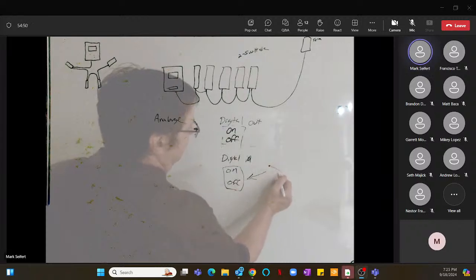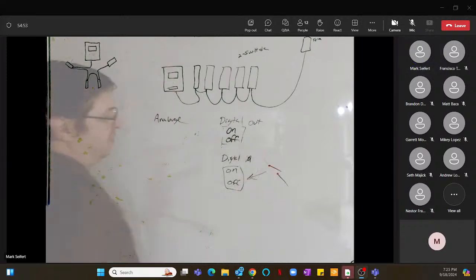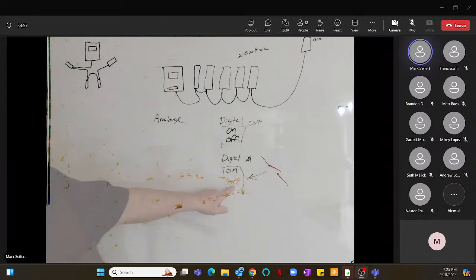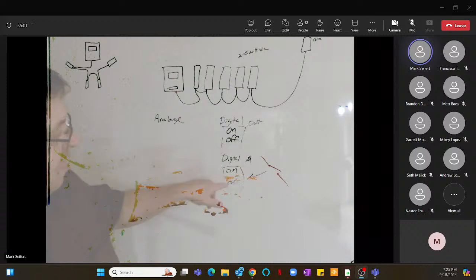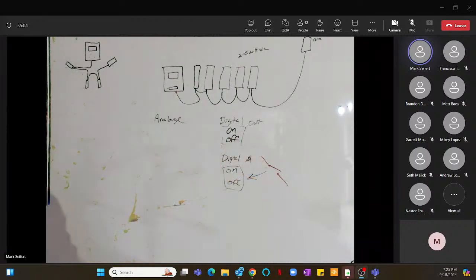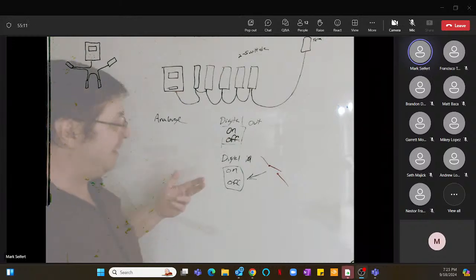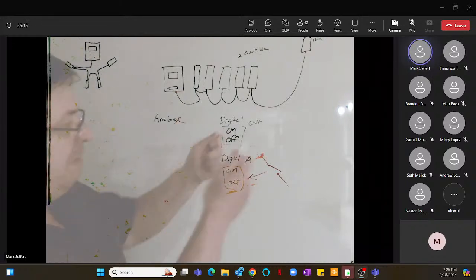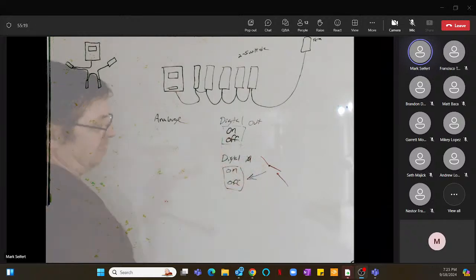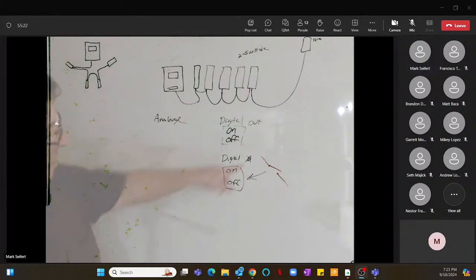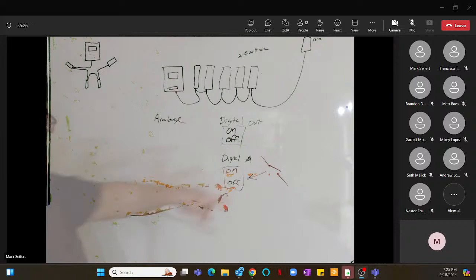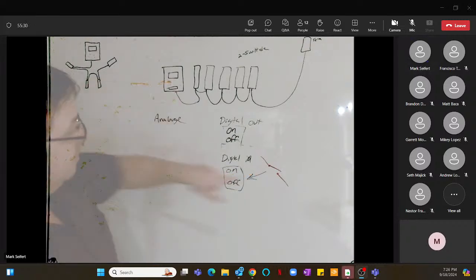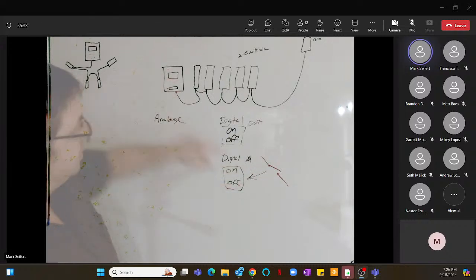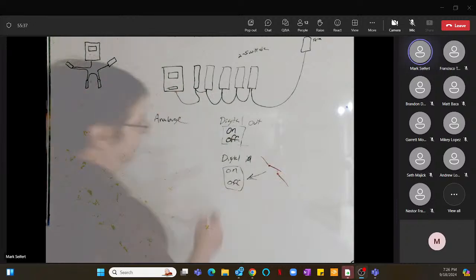Let's just do like a switch. That switch is open, that would register as off. There's very little voltage in there. You're going to read voltage in there, but what it's really reading is the resistance in there, for lack of a better word. It's reading an open circuit, just like as you take your meter and you check across that switch, your meter knows it's open. This does too, it sees it as off. Tells the computer brain that switch is open. That's all it's doing, digital in. Close it, now it's on. Computer knows it's on, that's a digital in.